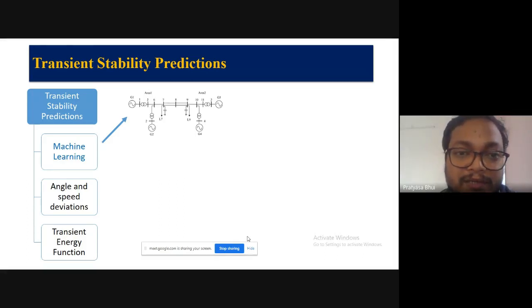So in a traditional SCADA system, the data are sent once per 2 or 3 seconds. Here it is 50 times a second, and all the data are time synchronized. So at one instant you will get a snapshot of the entire system. So you have the time as well as the data. So at one particular instant you have the data of the entire Indian grid. So how will you use that data for prediction of transient stability, or to take control actions?